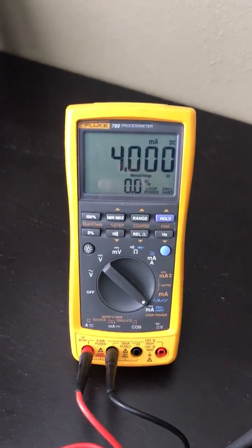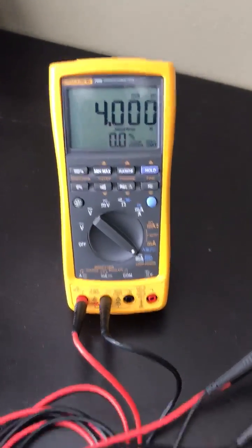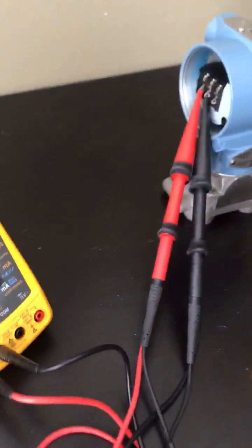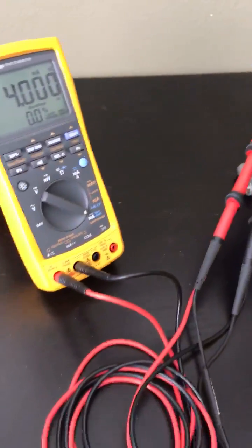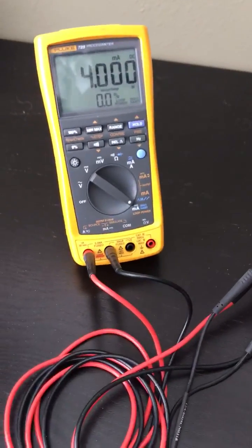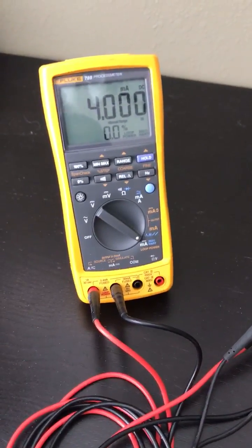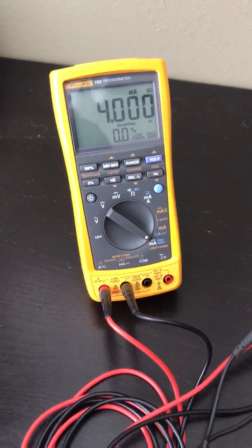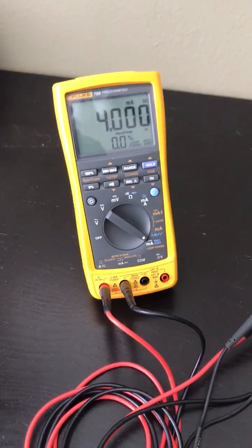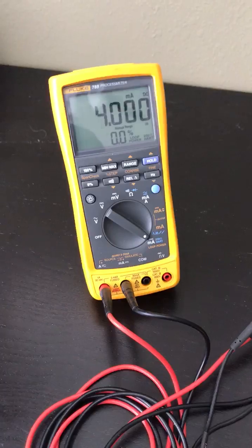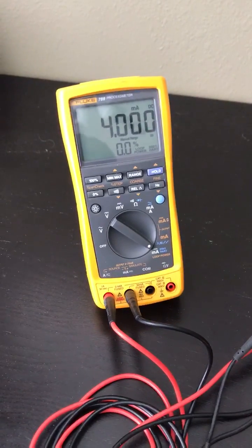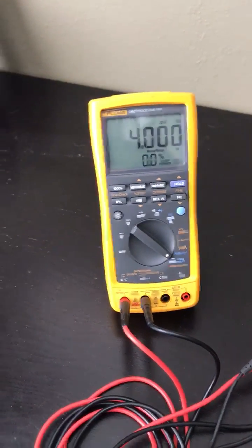A Fluke 789 process meter can be wired into the back of the transmitter to, in this case, read the 4 milliamp output of the transmitter and, in this case, provide 24 volt loop power and 250 ohms of resistance because I'm set up on a bench.